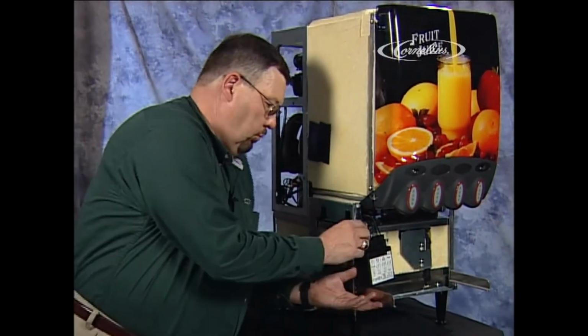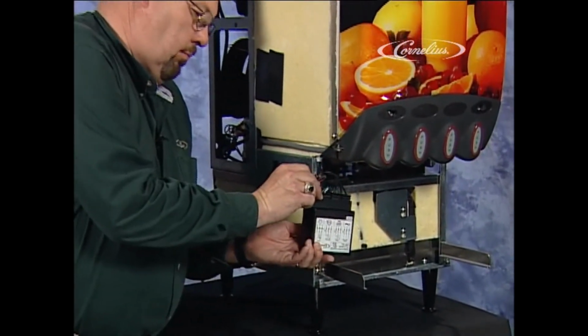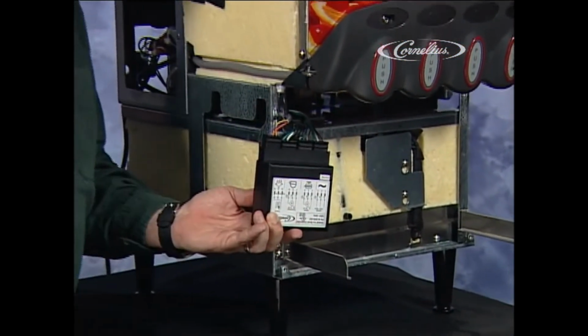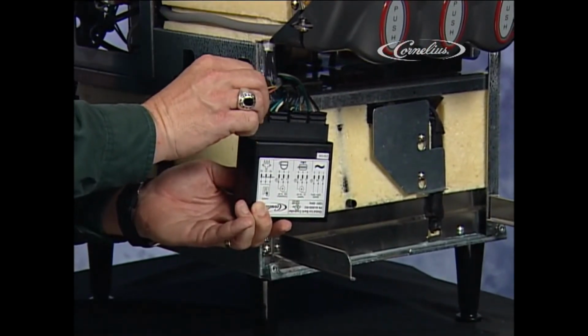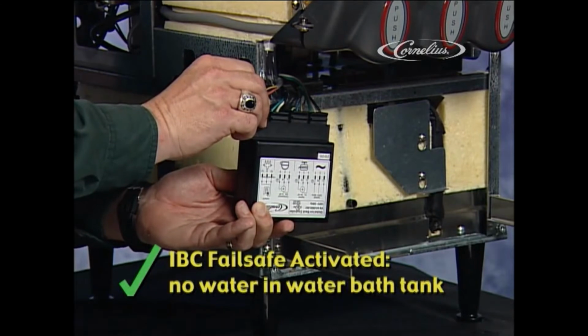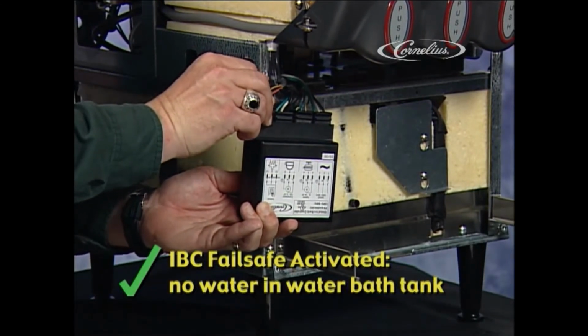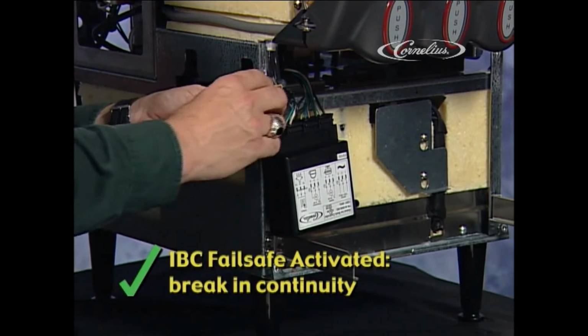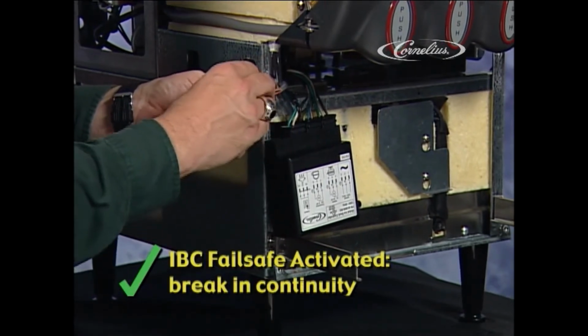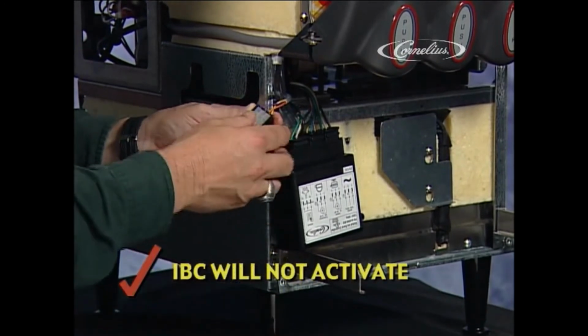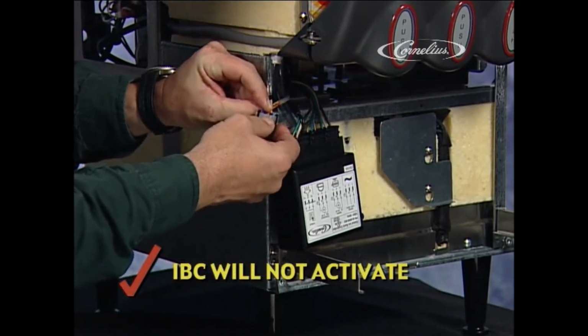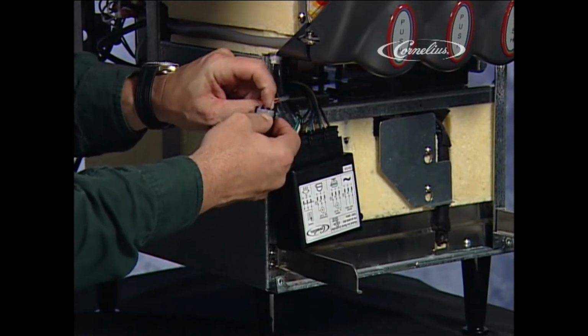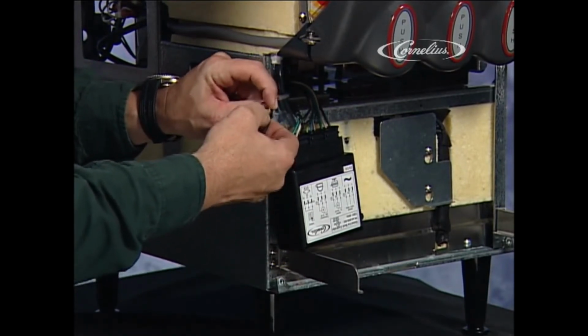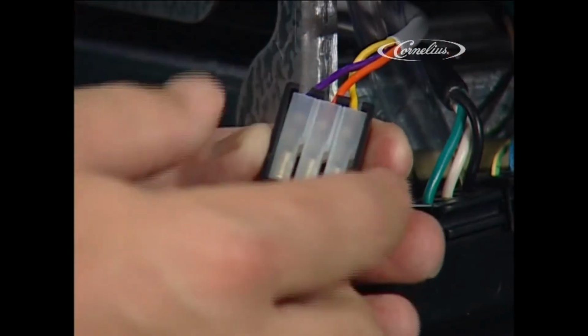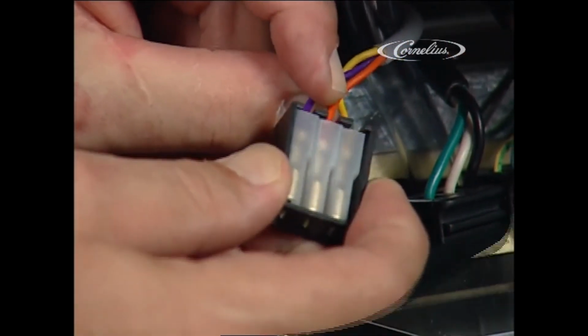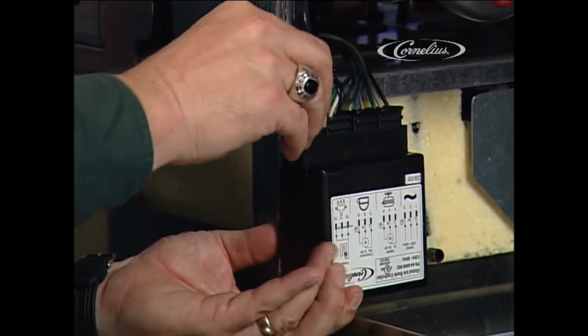Now we plug the probe back into the IBC and, with the unit plugged in and a full water bath, wait the 3 minutes. The refrigeration system should turn on. The fail-safe mode on the IBC is activated when there is no water in the water bath tank or there is a break in the continuity between the end of the probe and the connector, as in a broken wire, on any one of the legs. If this is the case, the IBC will not activate and the compressor and condenser fan will not come on. Inspect the wire connectors for any loose or bare wire. A slight tug test on each connector could expose this issue. Be sure, however, when replacing the connector, you get the wires in the proper order.